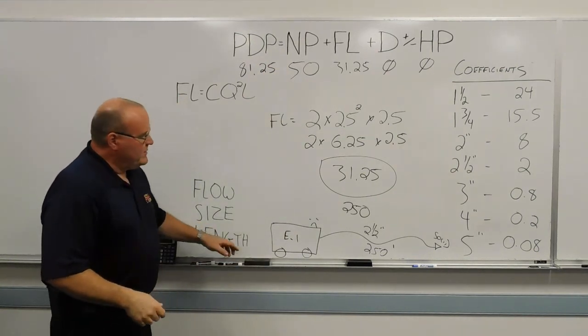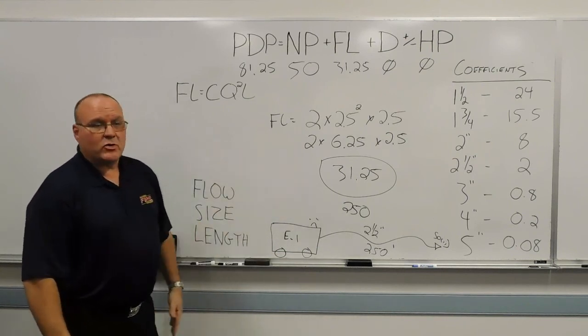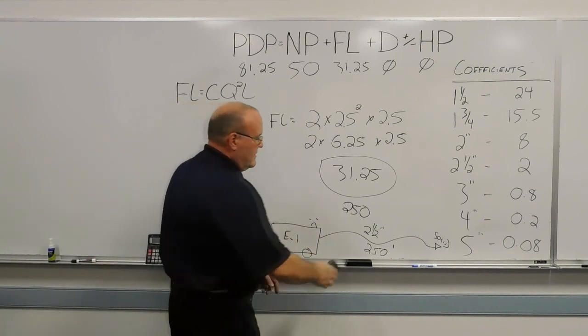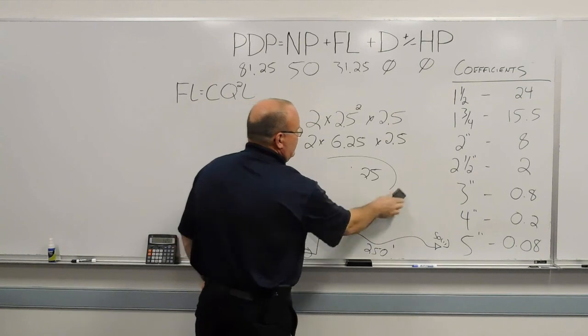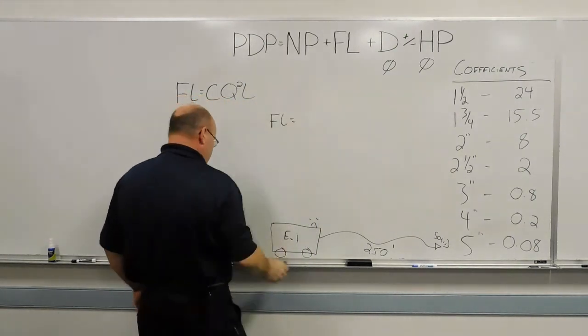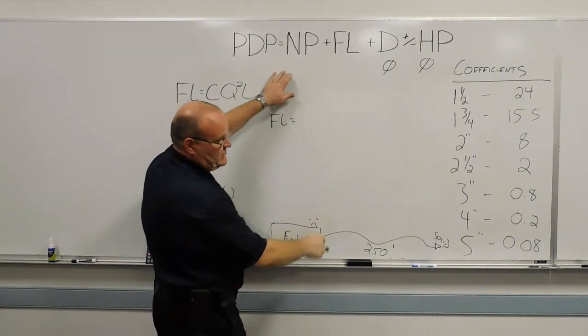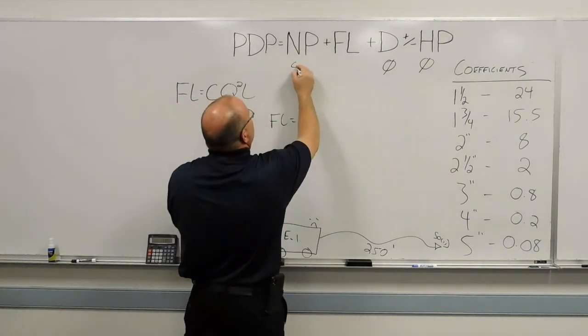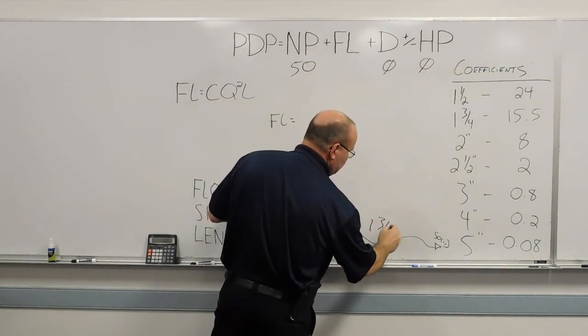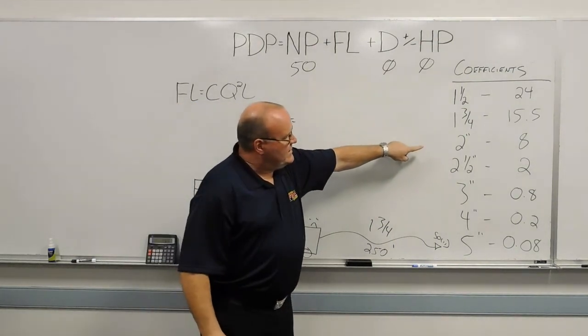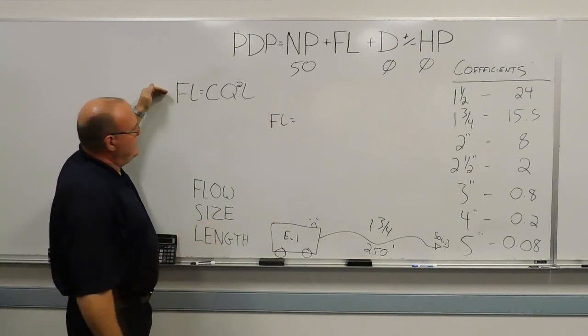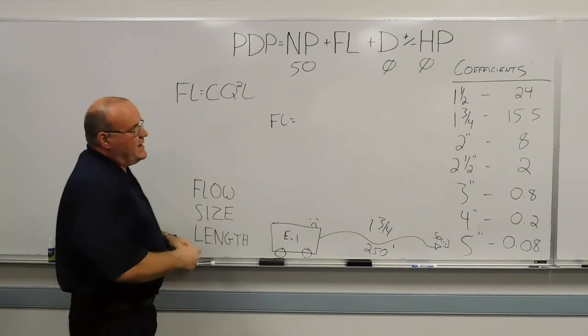We'll do one more example. And this time we're going to change our hose size and use inch and three-quarter. So same engine, we'll keep the same length, and we'll keep the same nozzle. So our nozzle pressure being the same, if it's a solid stream hand line, 50 pounds. We're going to change that from 2.5 to inch and three-quarter. And then our inch and three-quarter coefficient is 15.5. So friction loss, using the coefficient method, C, Q², L. The C part of that is 15.5.